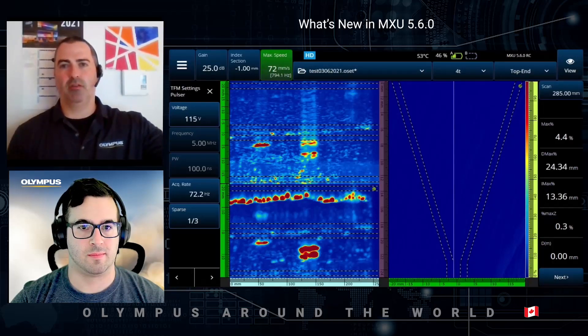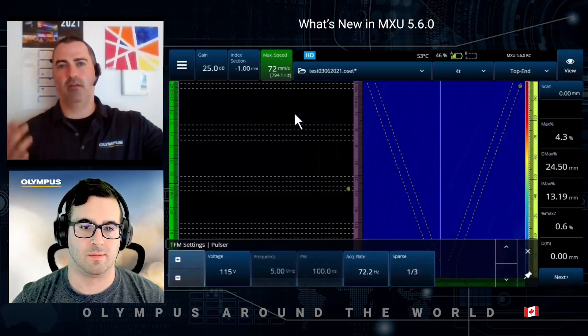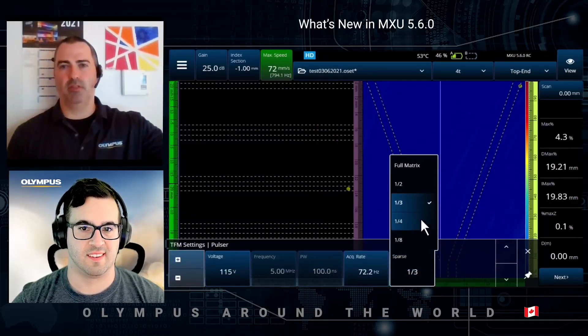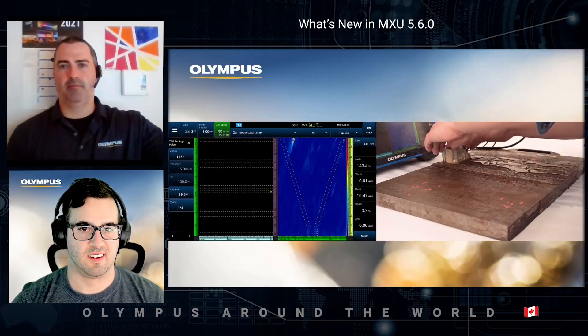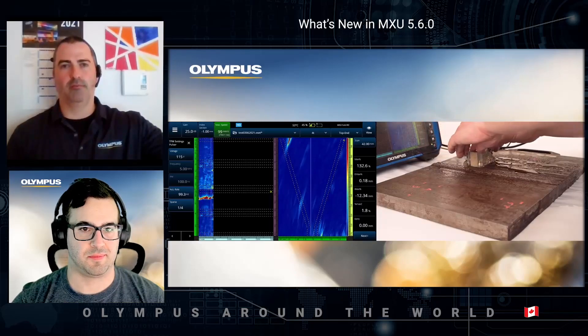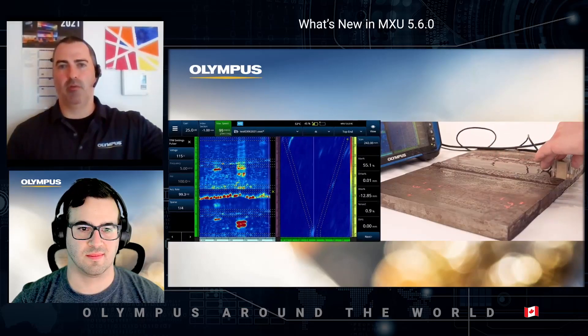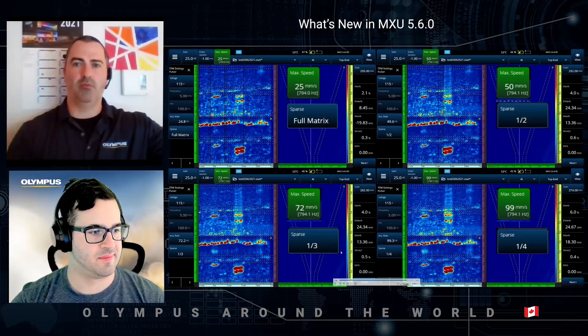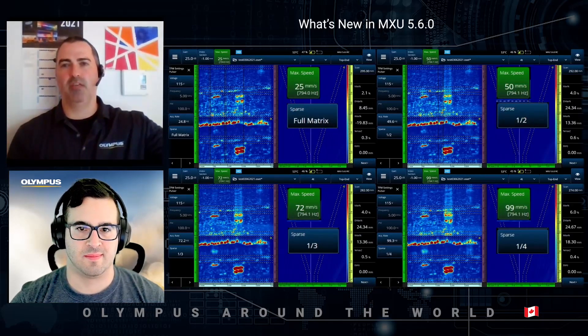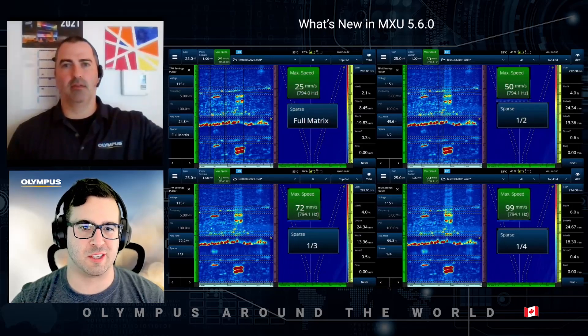This acquisition strategy can make TFM technology more accepted in the market — one of the big drawbacks has been the productivity of this technique. Now with two groups we can reach 100 millimeters per second, which is commonly accepted as a very good manual scanning speed for this kind of situation.